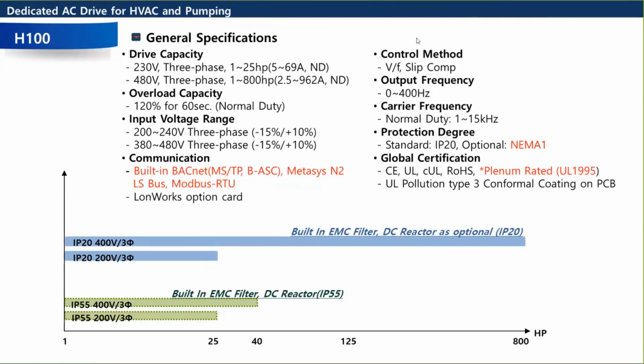The input voltage range, we've got two of them. We've got the 230 volt class, which is good for 200 to 240. So that'll cover 208, 230, 240, and everything in between. And then we have the 480 volt one, which goes all the way down to 380 because it is a global product. Most of us over here will probably be using 480 volts. So something in red here is the communication: we have a built-in BACnet. The H100 drive is the only LS drive with the built-in BACnet. It's MSTP. We don't have the BACnet IP yet. That's something that I believe we're working on, or it's on the list.